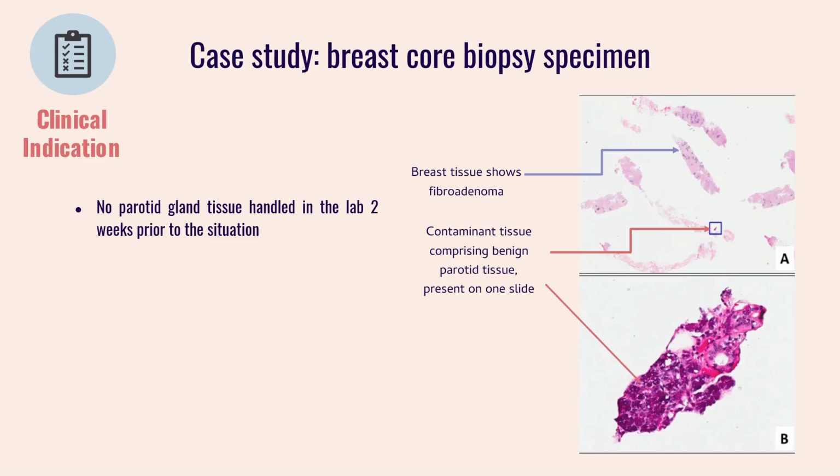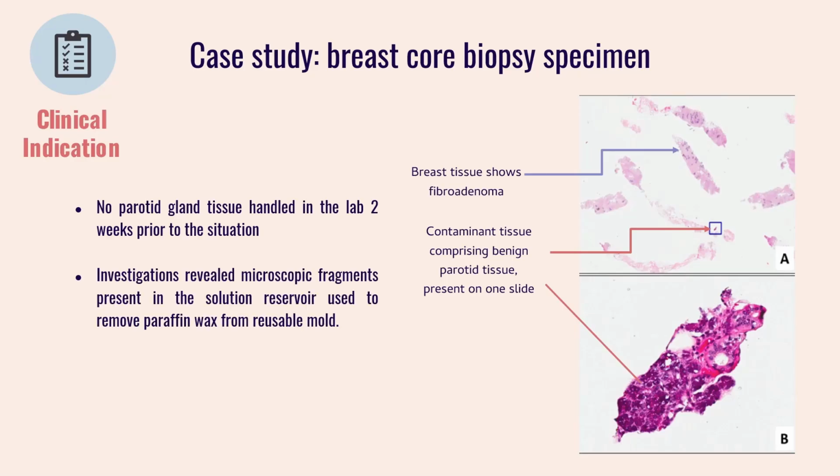In this particular case, investigations revealed that there was no other parotid gland tissue handled in the lab during the 2 weeks prior to this situation, making contamination at the water bath essentially impossible. Given this, a complete detailed step-by-step review of the in-house workflow was performed, which revealed that the reservoir of the solution used to soak off paraffin wax from reusable molds harbored a number of microscopic tissue fragments, and was the source of contamination in this case.